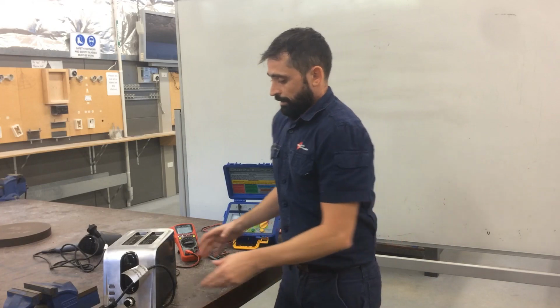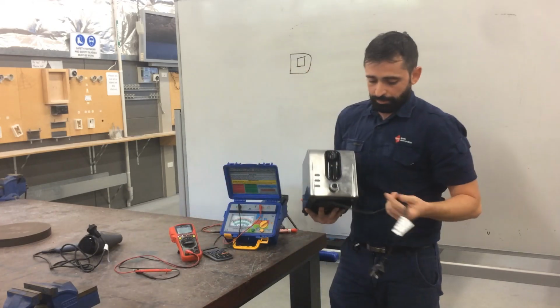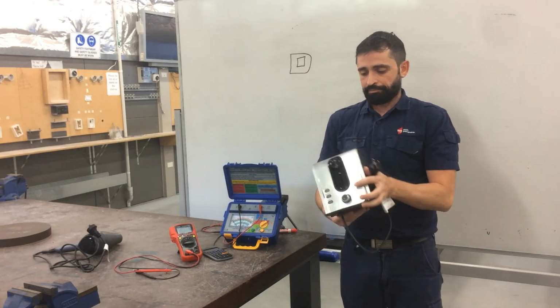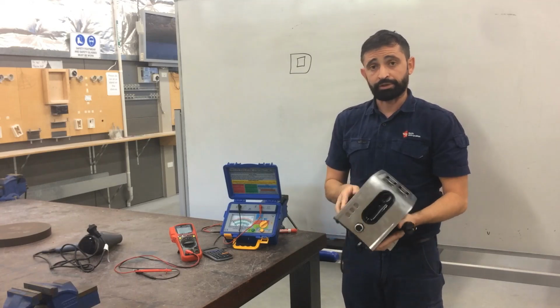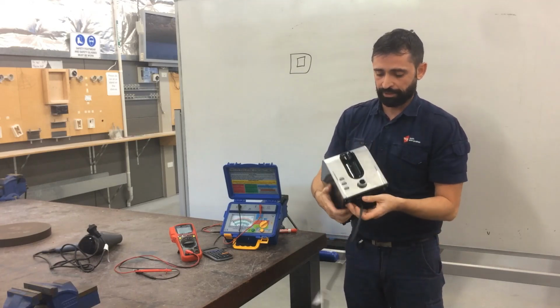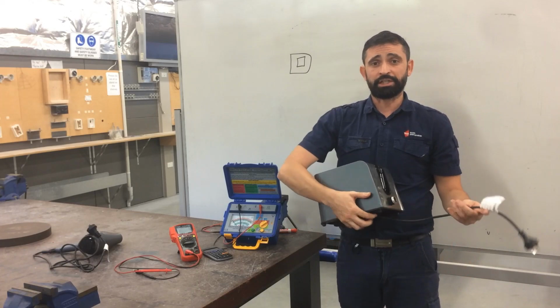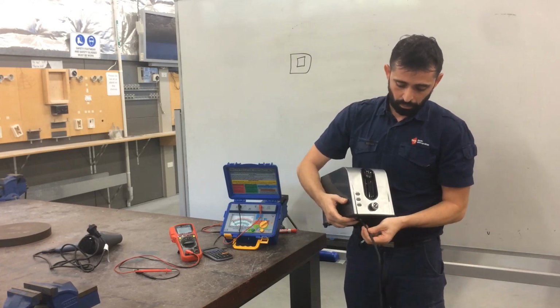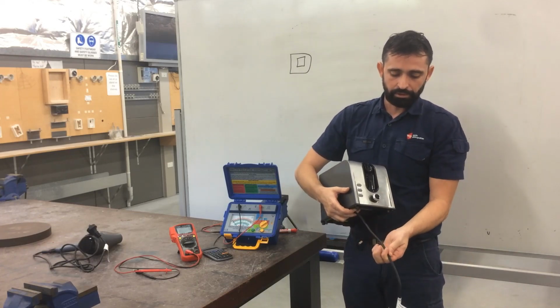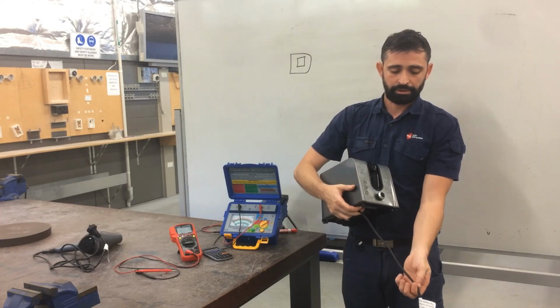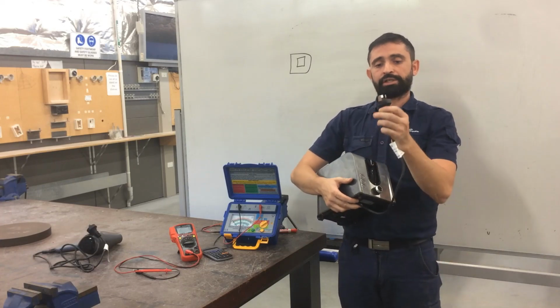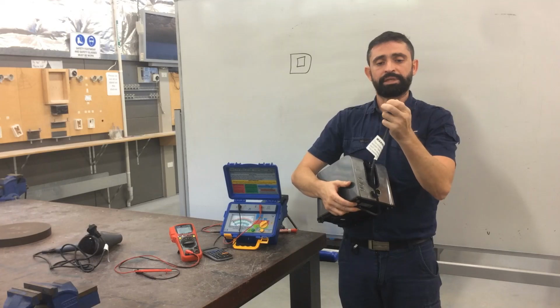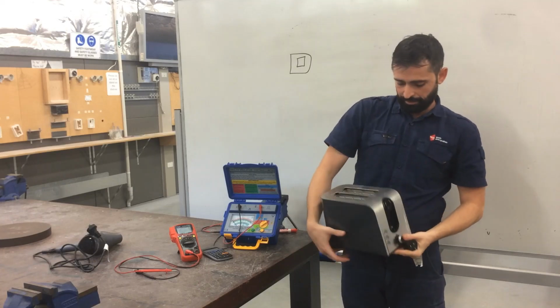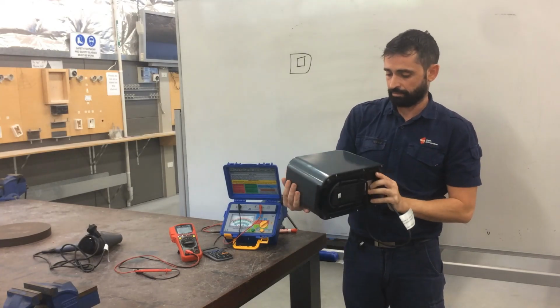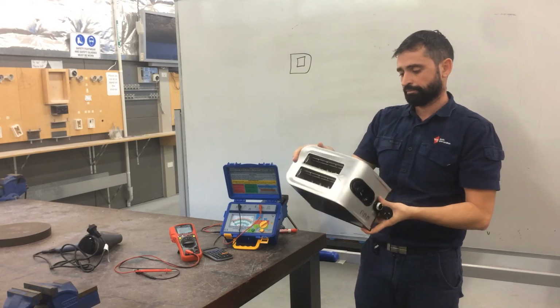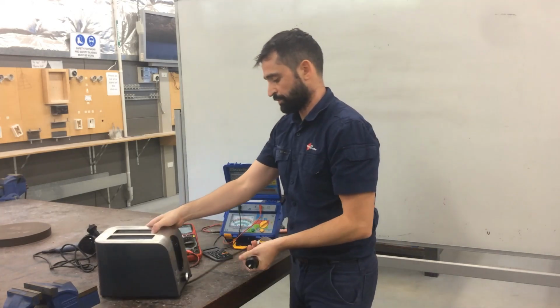Now, we're going to be doing our testing on the class 1 appliance today. So the first test we do is the visual inspection. The visual inspection finds 90% of faults. So what I'm going to do is rub my hand along the cord. I'm looking for any nicks. And then I'm going to check the base of the plug top, make sure the pins aren't bent, everything's there. You're also looking for any massive knocks that could potentially damage it. So that seems fine. The visual inspection is fine.